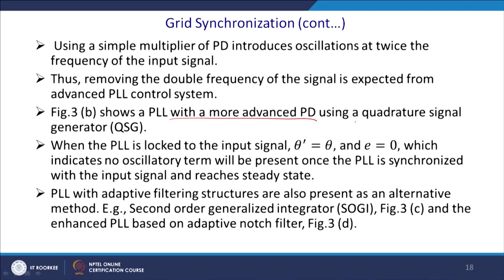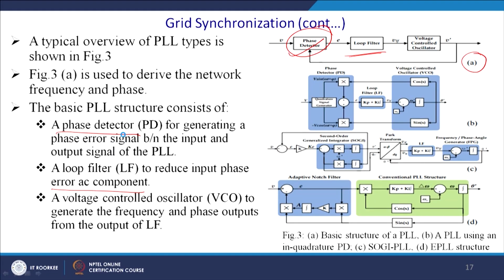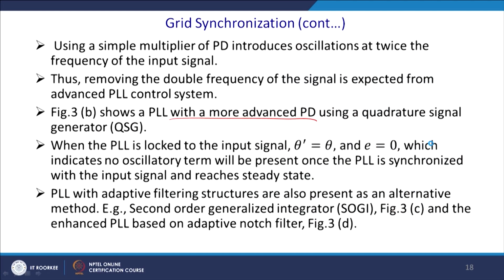And then figure 3b shows the PLL with a more advanced PD, phase detector, using a quadrature signal generator, QSG. So, let us go back. This is basically the quadrature signal generation, QSG. Ultimately, you get sin theta and cos theta, then you multiply sin theta and cos theta, and there is a PI controller that will generate the loop. So, instead of a simple multiplier, the quadrature signal generator QSG has been used.